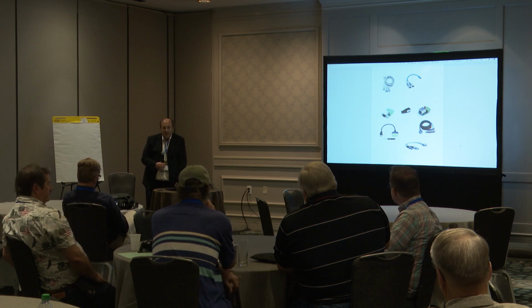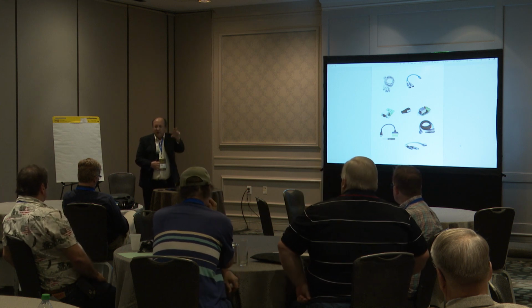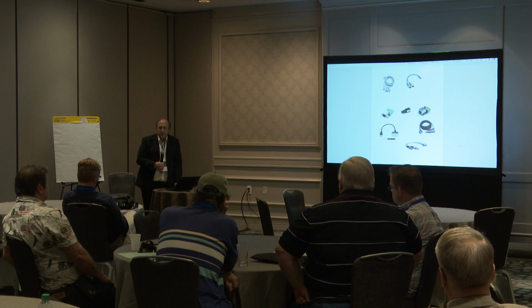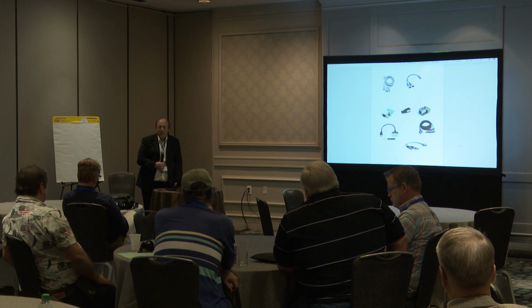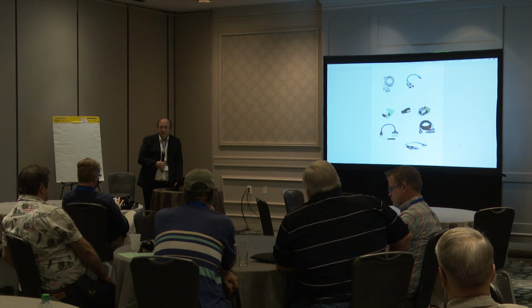And I have been to facilities where they were beautiful. All the wire was Z-folded in 90 degrees, and I had to cut all of it and replace it because it was interfering with either a copper signal or a fiber signal. There's plenty of resources on the web for the proper way to install cable. If you're putting 90 degree bends in things, you're going to have a problem.